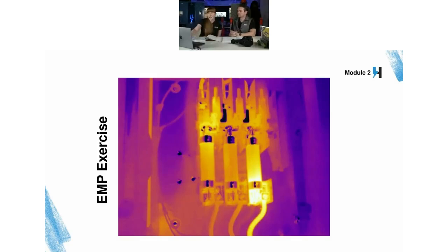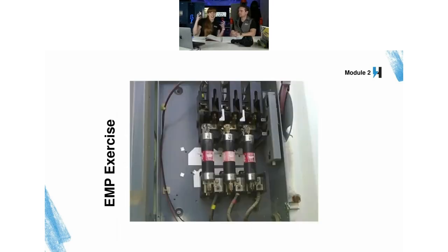Essentially, you can't tell that it is that hot, that big of a difference between the cold or room temperature stuff and the heated point just by looking at it. That's why you have to get that infrared scan done minimum every year.